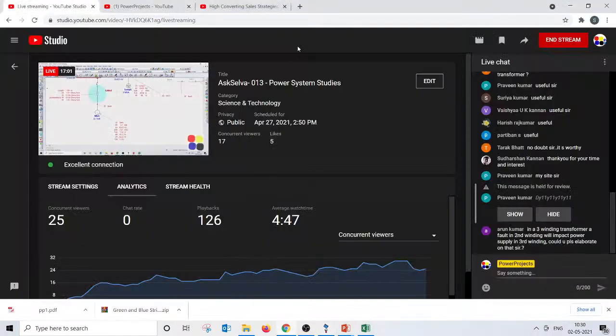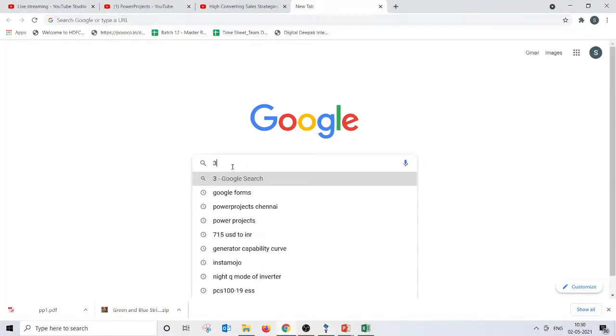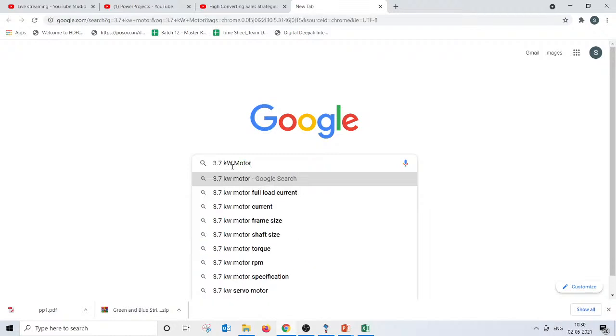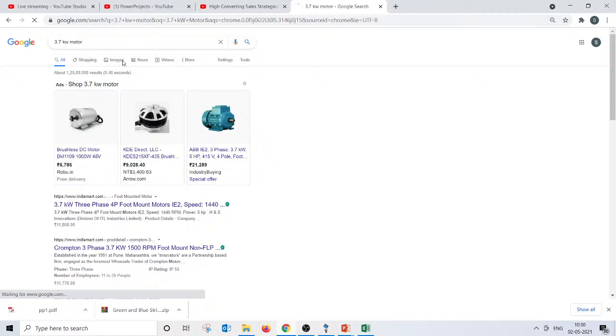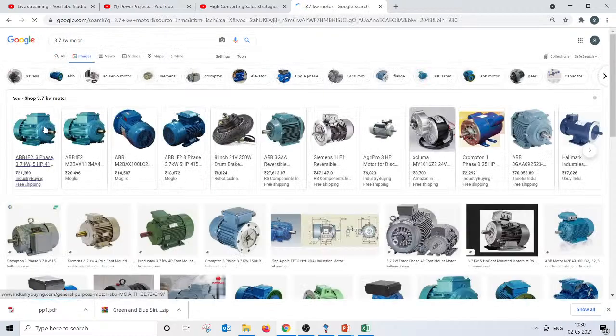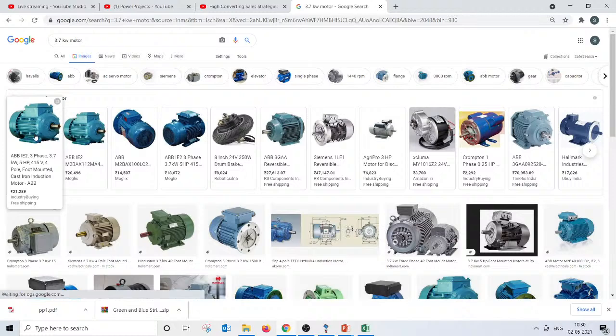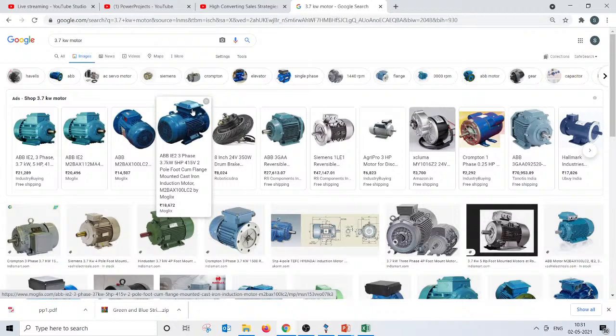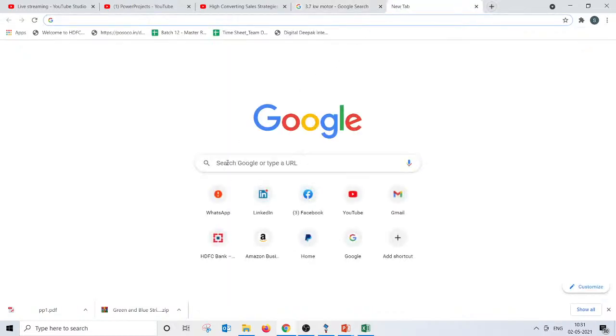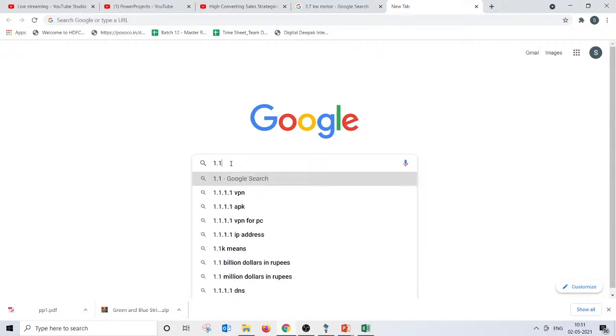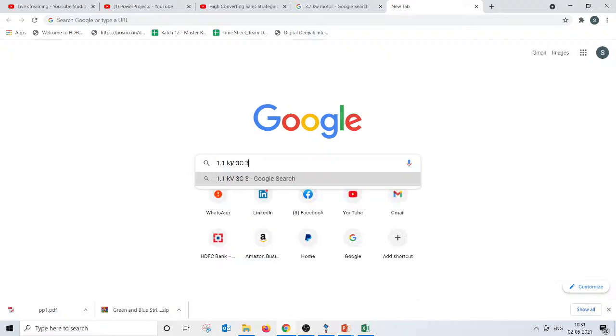Let's look at some interesting sizes of the motor. Yeah, this could be approximately a 3.7 kilowatt, that is 5 HP motor. It will cost Indian rupees about 21,000. And you can see this cable terminal box at the top, and you can imagine the size of a 35 square cable, 1.1 kV, that is in India. Yes, but you can go with 1 kV grade, that is as per IEC as well. 1.1 kV grade, 3 core, 35 square cable.